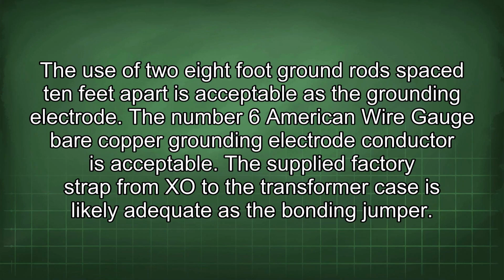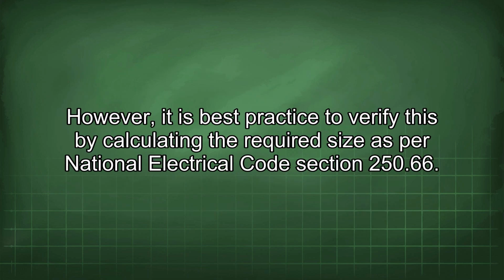The use of two 8-foot ground rods spaced 10 feet apart is acceptable as the grounding electrode. The number 6 American wire gauge bare copper grounding electrode conductor is acceptable. The supplied factory strap from XO to the transformer case is likely adequate as the bonding jumper.